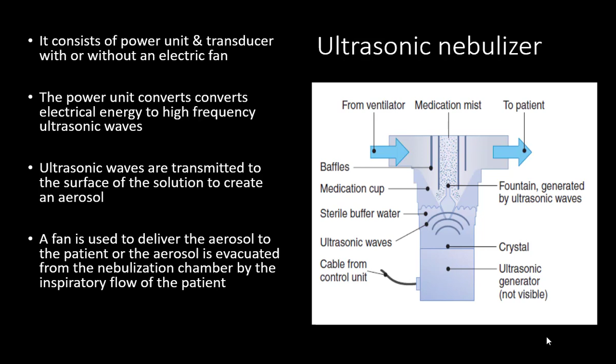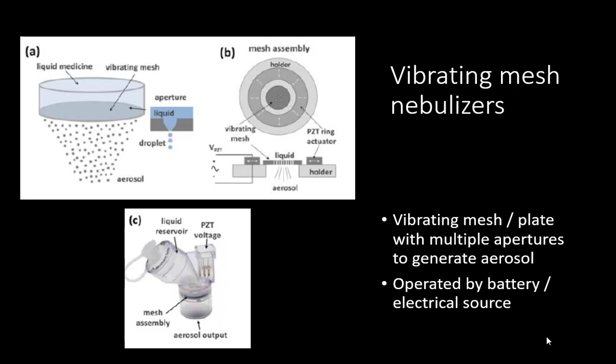So nowadays you should use vibrating mesh nebulizers. The reason behind this, we'll come to it. This is a mesh plate which has a lot of apertures. The AeroNeb nebulizer which is available in Medanta has around 1000 apertures. So the vibrating mesh plate keeps on vibrating with multiple apertures to generate aerosol. The advantage is it does not require an electrical source. It can be operated by a battery itself.